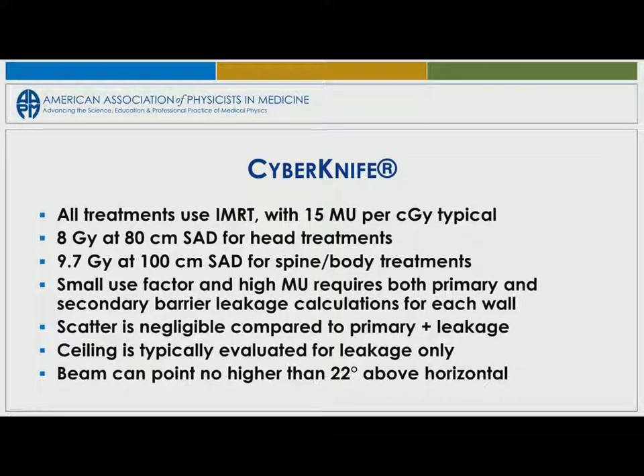Now, if you have that smaller field size, what does it do to your scatter factor? Well, scatter factor becomes almost negligible, because when we shield normally for a traditional LINAC, our field size is assumed to be a 40 by 40 centimeter. So you have a large scatter fraction off of that patient. When you do a CyberKnife treatment, because you have such small fields, your scatter factor is significantly smaller. And the ceiling is only for leakage, because you can't point the CyberKnife at the ceiling. So it really does save you some shielding.